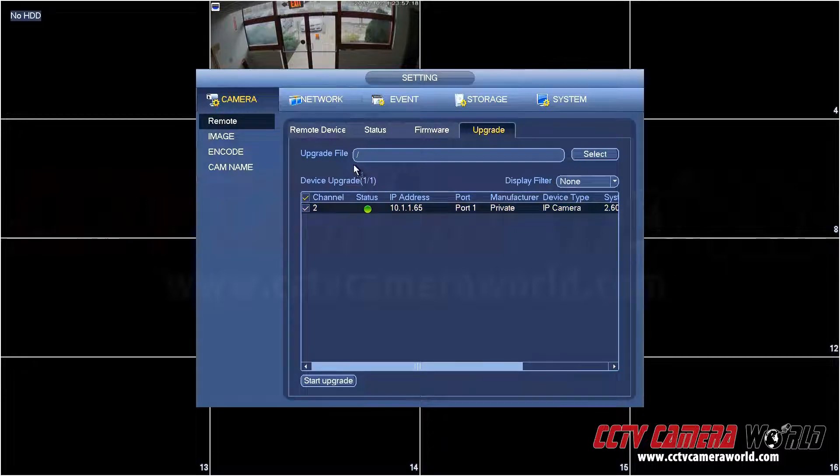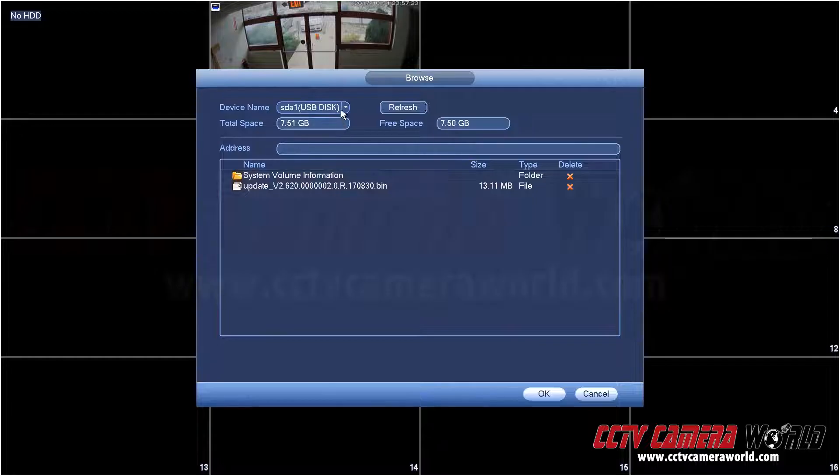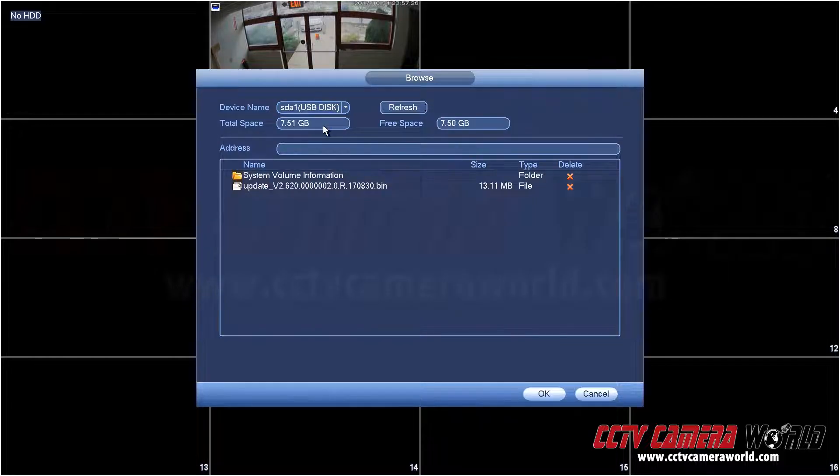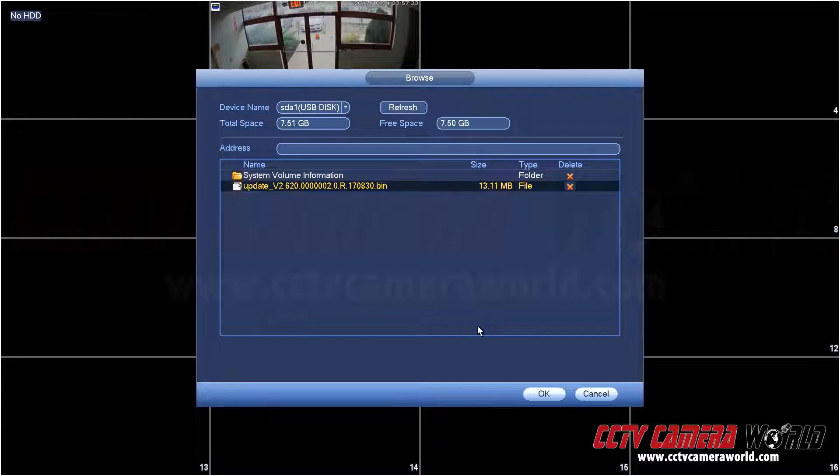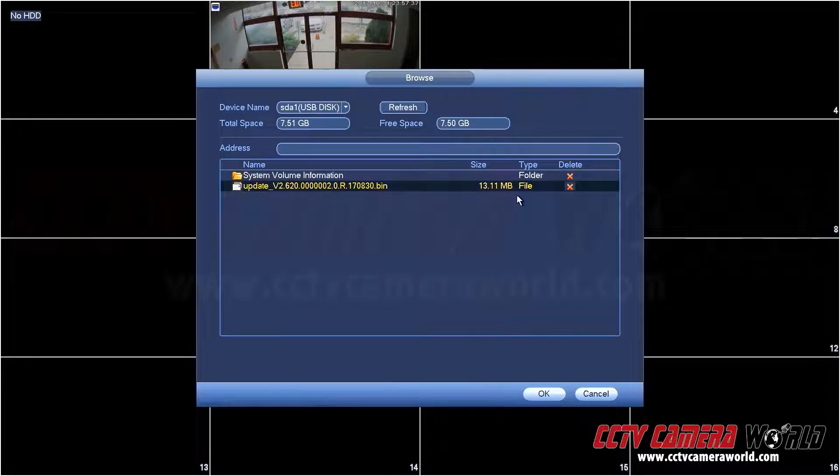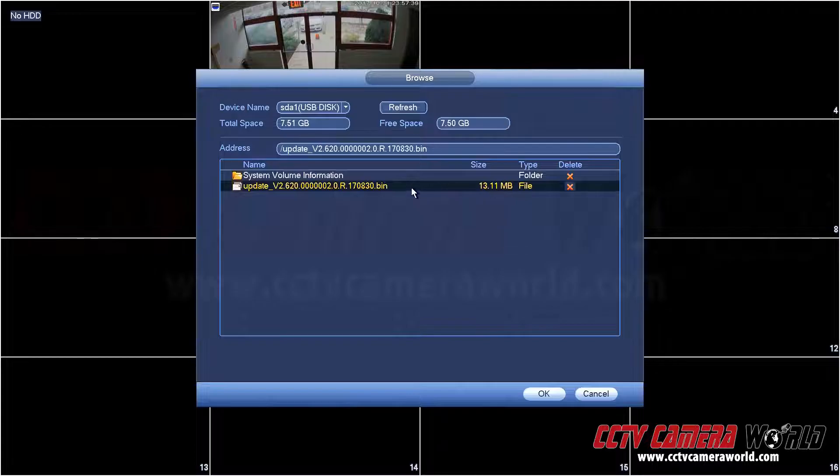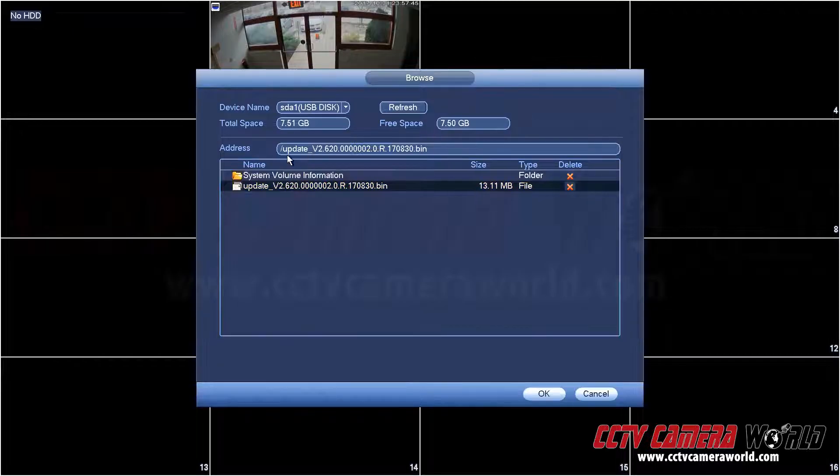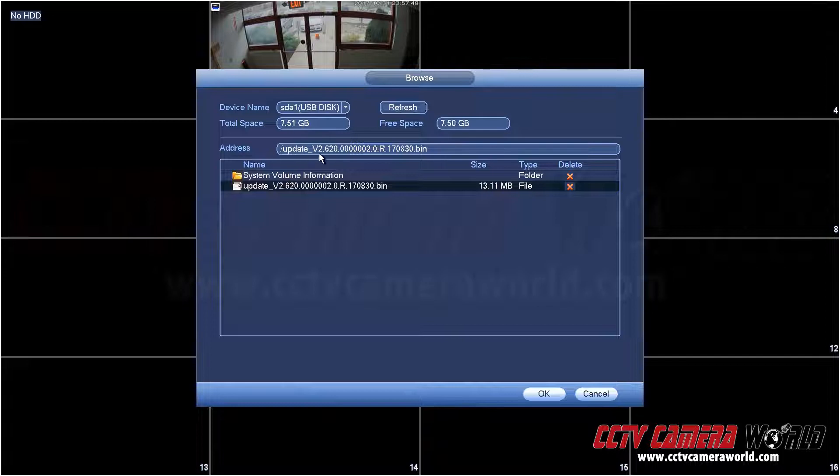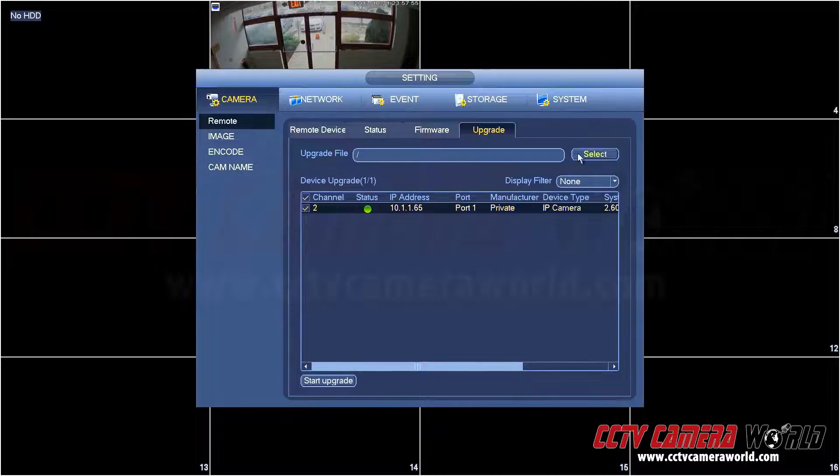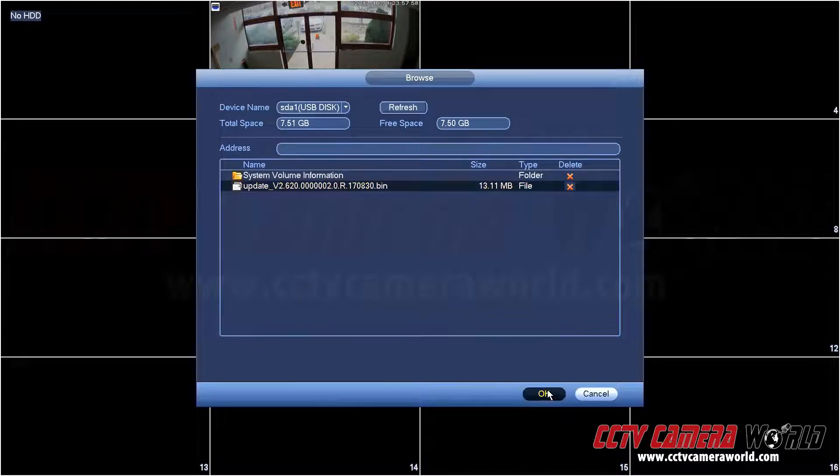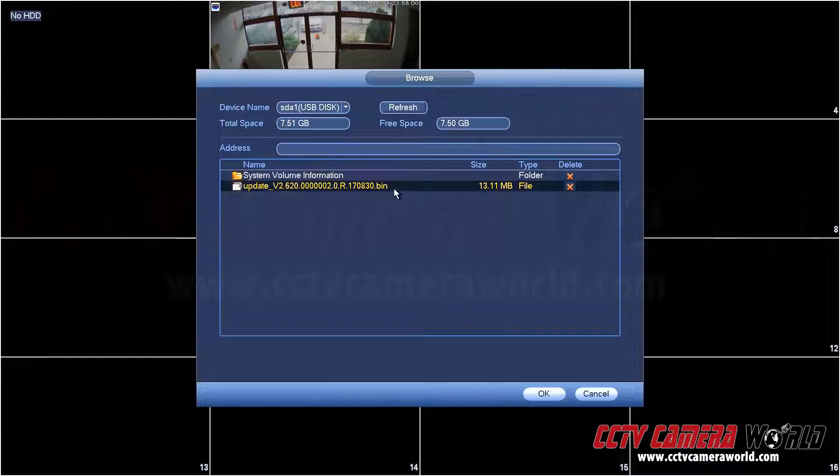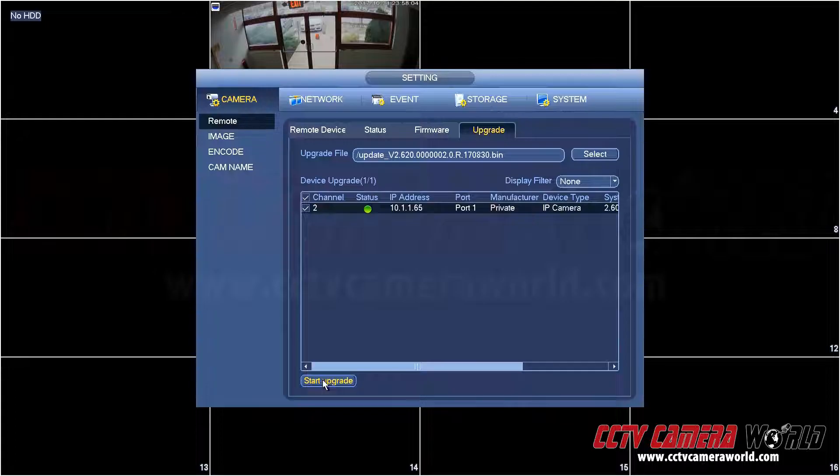Here I'm going to select the checkbox, press select, and navigate to your flash drive. In this case on the top it says my USB disk and I have my firmware located in the root directory. I'm going to select it and then hit OK. You have to double click. If you just press OK it won't let you proceed to select the file. You have to double click on the file and now it says in the address bar the file name. That means the file has been selected. Let me show you that again. I go to select, I click once, and if I press OK it's going to give me that error. Make sure you double click, press OK.